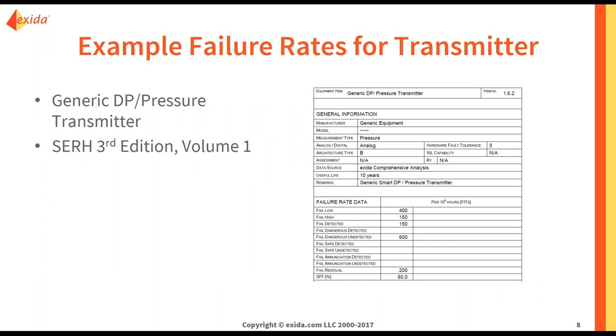Here is a screenshot of our Safety Equipment Reliability Handbook. If you are familiar with exida or our SERH, you might be familiar with this data sheet. It is showing the failure rates for a generic pressure transmitter. Instead of classifying these failures as safe or dangerous, it is classifying them as fail low, fail high, fail detected, and fail dangerous undetected. I am going to show you how these failure modes can be applied to your system and classified correctly.